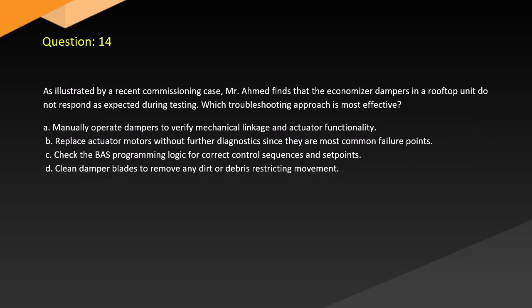Question 14. As illustrated by a recent commissioning case, Mr. Ahmad finds that the economizer dampers in a rooftop unit do not respond as expected during testing. Which troubleshooting approach is most effective? A. Manually operate dampers to verify mechanical linkage and actuator functionality. B. Replace actuator motors without further diagnostics since they are most common failure points. C. Check the BAS programming logic for correct control sequences and set points. D. Clean damper blades to remove any dirt or debris restricting movement.